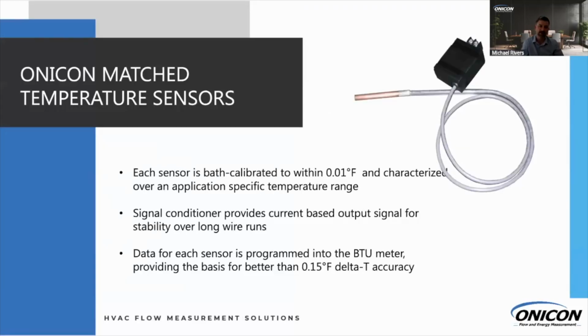So what ONICON does is we provide calibrated and matched temperature sensors. So the key word there is matched. You tell me you have a chilled water system with BTU measurement. Well, we take the 2 temperature sensors, we put them in the same bath against a NIST traceable master sensor. So each one will have its own slope and offset that we're programming into our BTU system. So now, even if it's a quarter degree off on the supply, it's a quarter degree off in the return in the same direction, which offers a really high-end BTU accuracy.